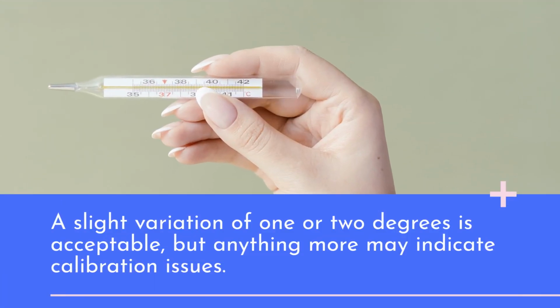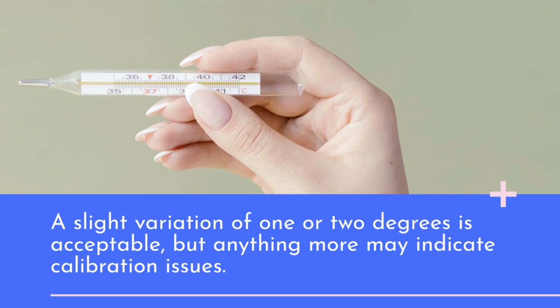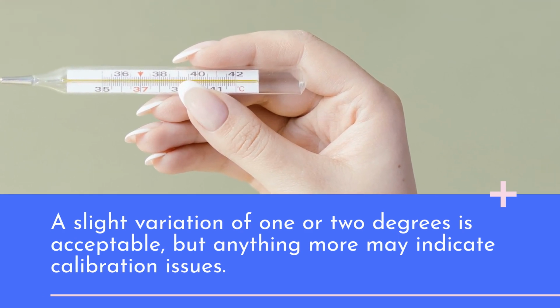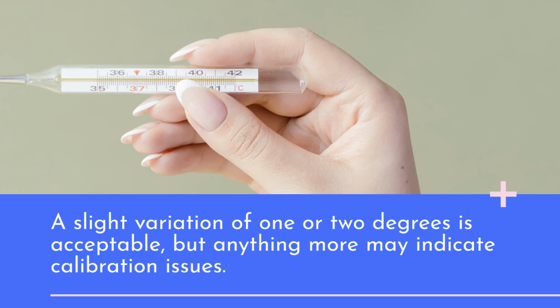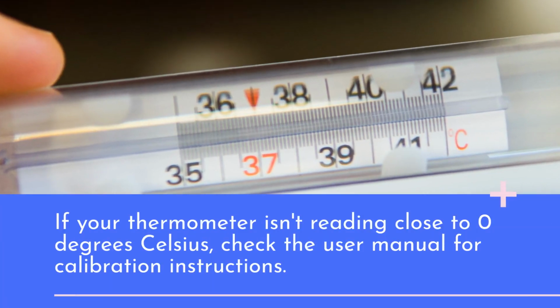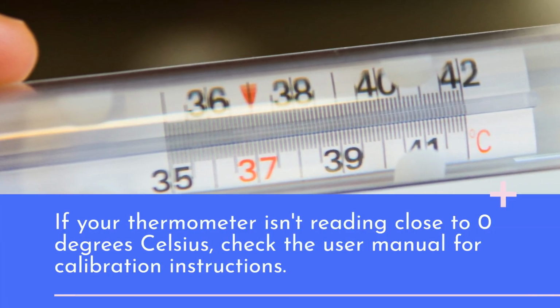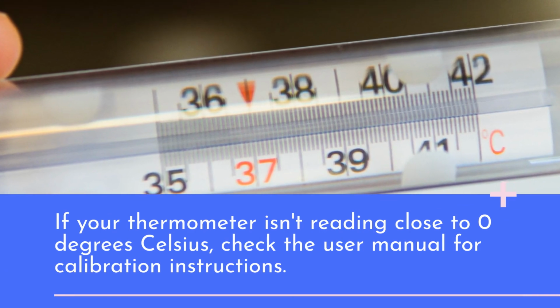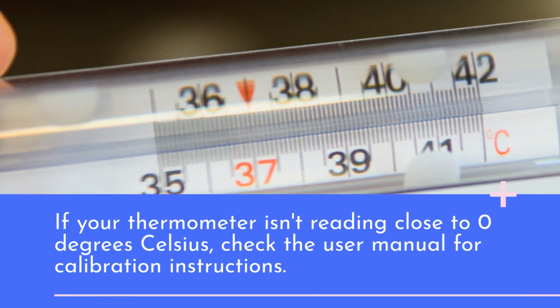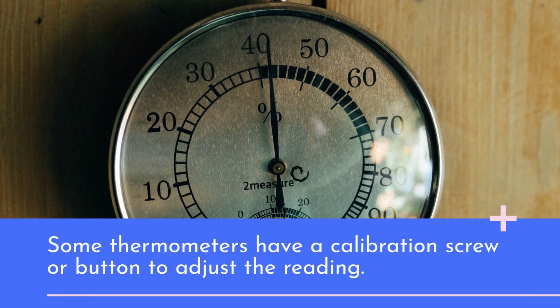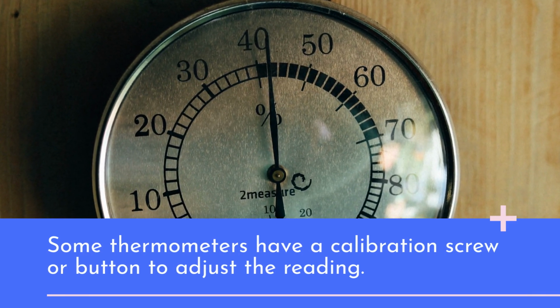A slight variation of 1 or 2 degrees is acceptable, but anything more may indicate calibration issues. If your thermometer isn't reading close to 0 degrees Celsius, check the user manual for calibration instructions. Some thermometers have a calibration screw or button to adjust the reading.